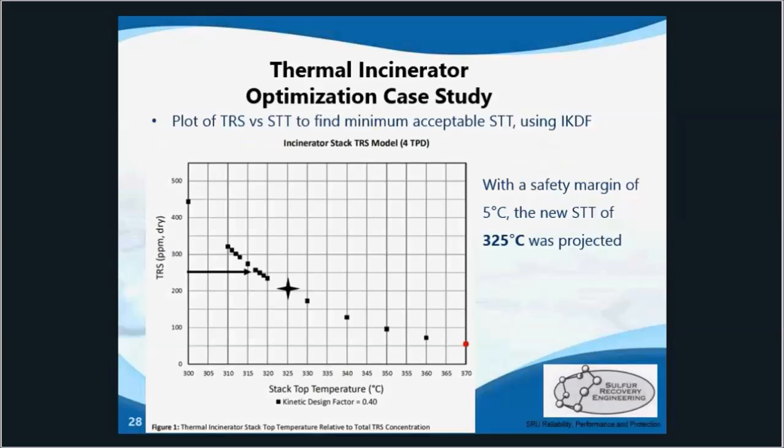This curve finds the minimum acceptable stack top temperature at the target of 250 ppm total reduced sulfur, TRS. Starting at 250 on the left and going over, that drops down from our curve at somewhere between 315 and 320 degrees Celsius. With an added 5-degree safety margin, we recommended the final acceptable temperature of 325 degrees Celsius.